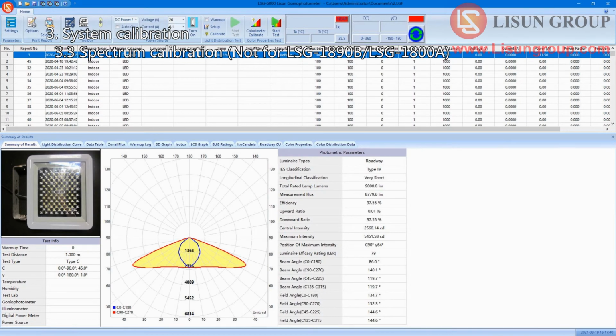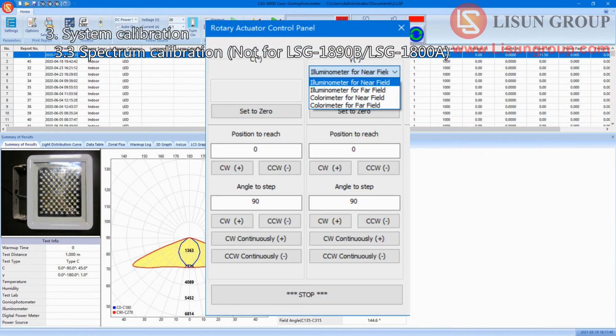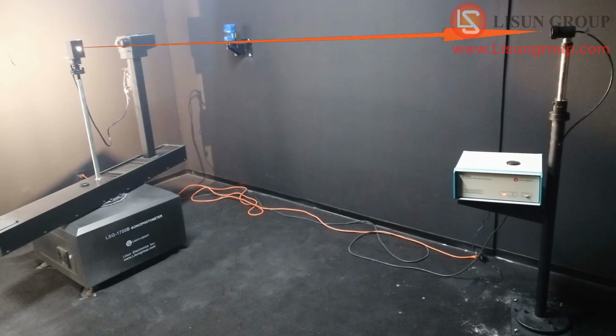Then we calibrate the spectroradiometer. Choose colorimeter for near field. Rotate the gamma angle to 0 degree position. Rotate the gamma angle 90 degrees clockwise or counterclockwise according to the actual situation. Make sure that the hole of the standard lamp holder faces the optical fiber.